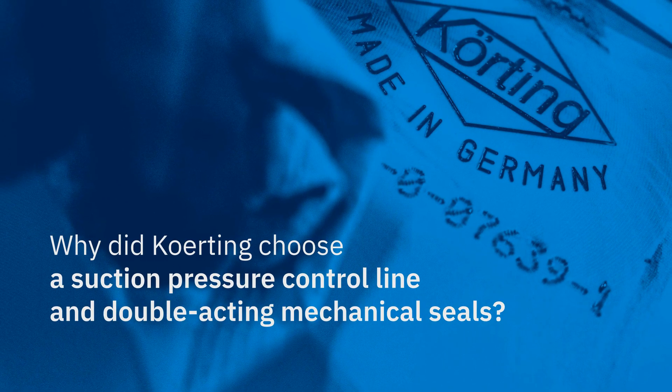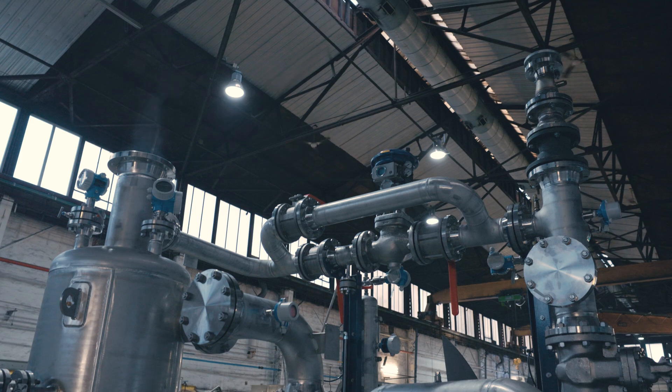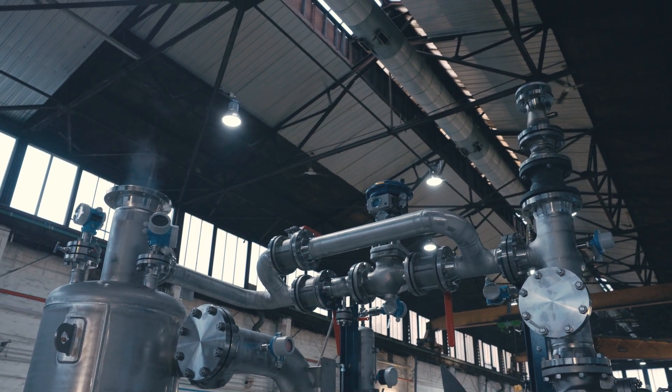Why did Koerting choose a suction pressure control line and double-acting mechanical seals? Cavitation can cause irreparable damage to internal components. In order to avoid that, Koerting recommends using a suction pressure control line that ensures the liquid ring vacuum pump never runs in non-permissible conditions, while also guaranteeing stable conditions throughout the entire operation.